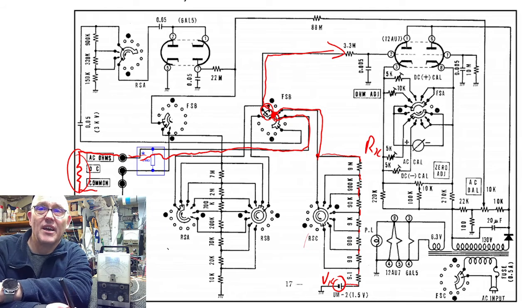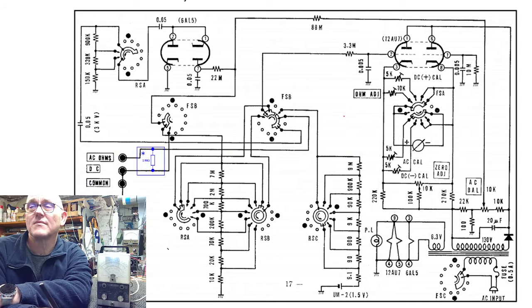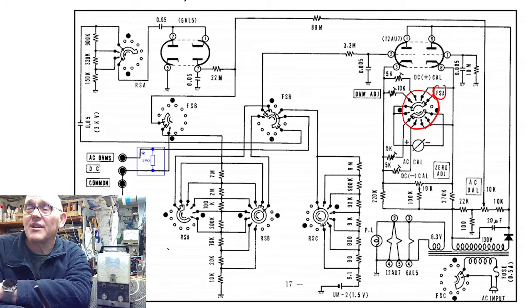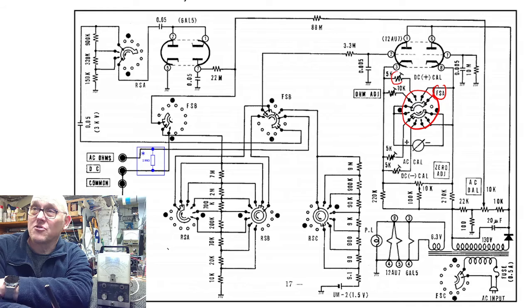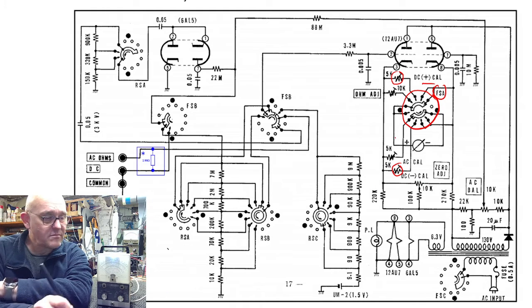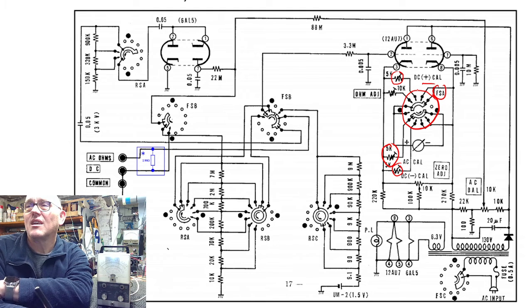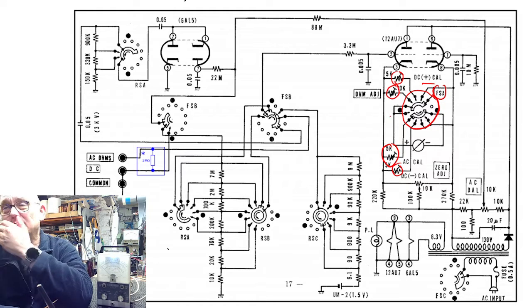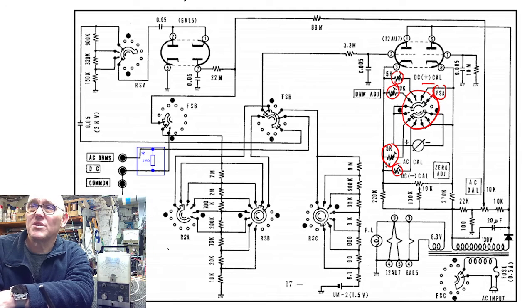So now I've covered DC, AC and ohms readings. Calibration takes place with this function switch A, and in this position the function switch is only there to select in and out the different trim pots for DC positive calibration, DC negative calibration, and this is only found on the Kyoritsu. I find the Heathkits don't have that negative calibration. AC volts calibration, and yeah, that's it. Ohms adjust. Now the voltage calibration is always set for full scale deflection.